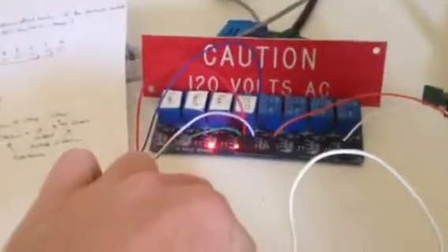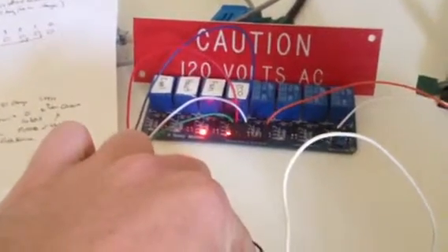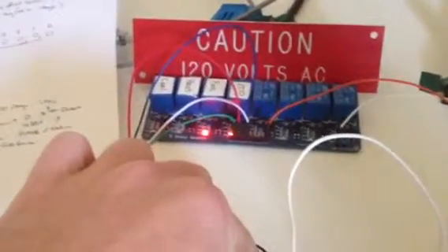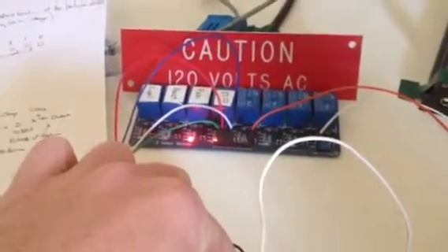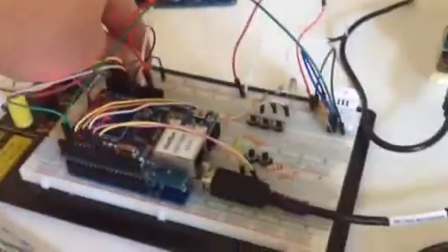whichever one comes faster, if the inside temp goes above 73 faster than the outside temp comes down, then everything will go off. But if the outside temperature goes down faster than the inside goes up, then the heat should trigger on, and then you'll see that this thermostat is working correctly. And now we wait for it actually to happen.